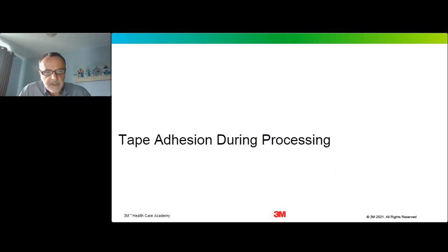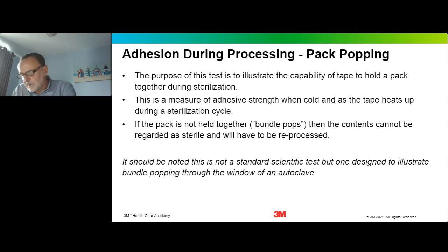So let's now have a look at tape adhesion during processing. The purpose of this test is to assess the ability of the tape to remain intact during a sterilisation process. In this test, it's often called a bundle or pack popping test. We attempt to illustrate the capability of the tape to hold the packs together during the sterilisation cycle itself. And this is a measure of the tape's ability to work when it's cold, but also when it's hot and subjected to moist heat conditions and big internal pressures.